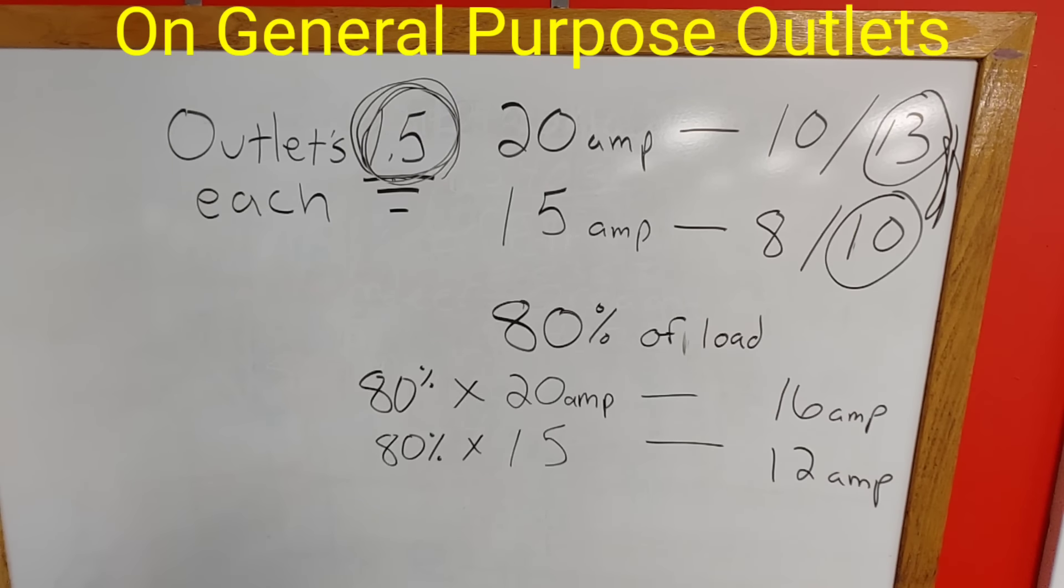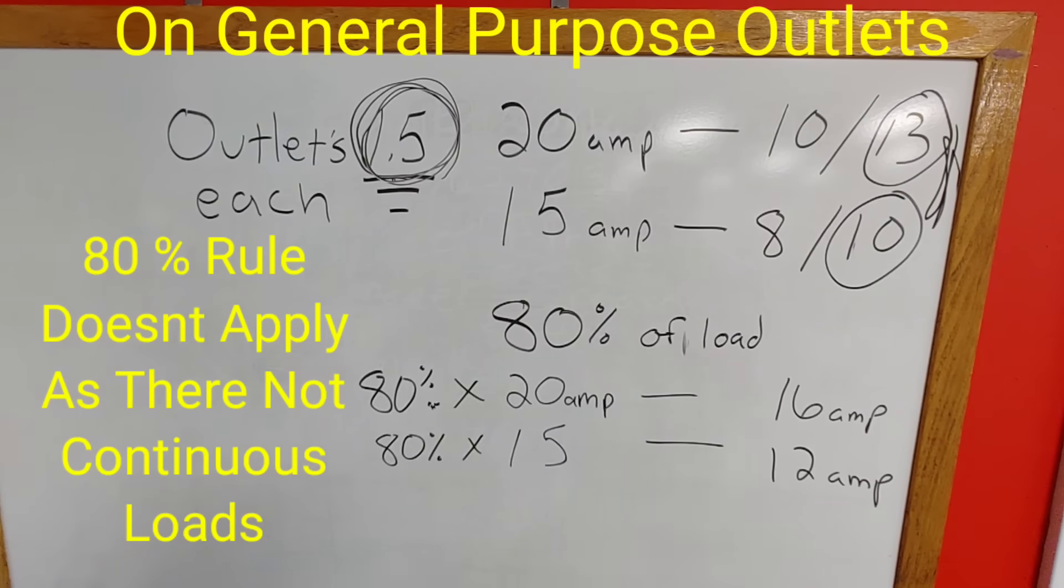But some people will also tell you, hey wait a minute, you can only use 80% of the load of that circuit. So 80% of a 20 amp circuit is 16 amps. 80% of a 15 amp circuit is 12 amps.